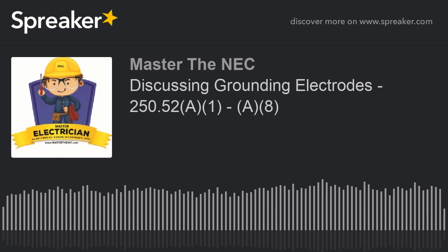If you still can't, then the electrode shall be permitted to be buried in a trench that is at least 30 inches deep. So that's just allowing you to lay it in the trench. Now, it also goes on to say the upper end of the electrode shall be flush with or below ground level unless the above ground end and the grounding electrode conductor attachment are protected against physical damage as specified in 250.10.